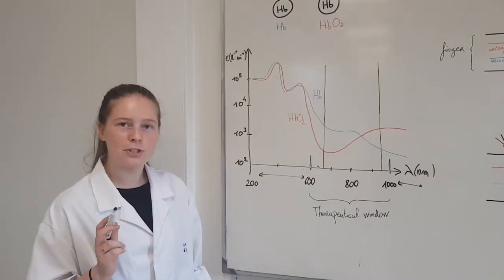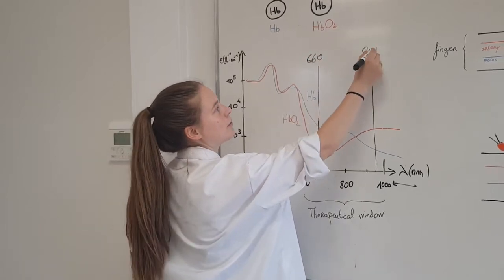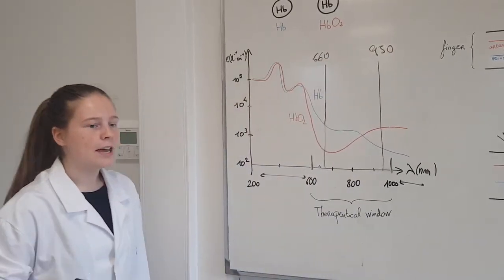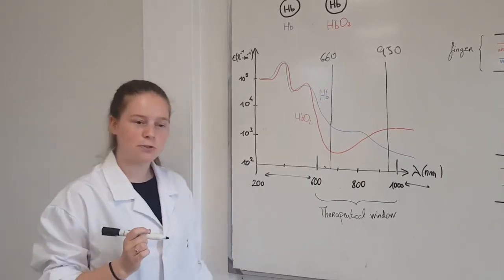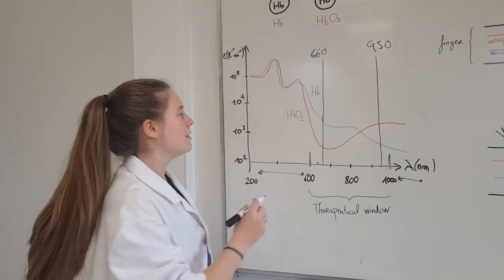The wavelengths we chose are 660 nanometers and 950 nanometers. These wavelengths were chosen so that the absorption rates of oxyhemoglobin and deoxyhemoglobin differ enough.